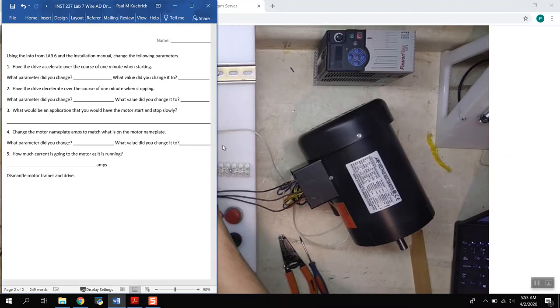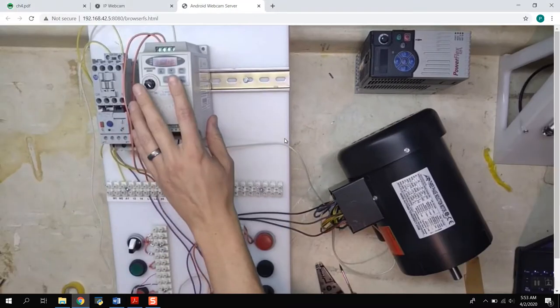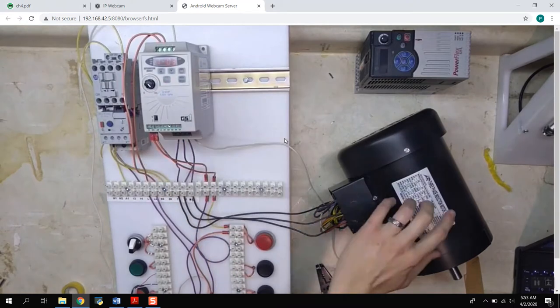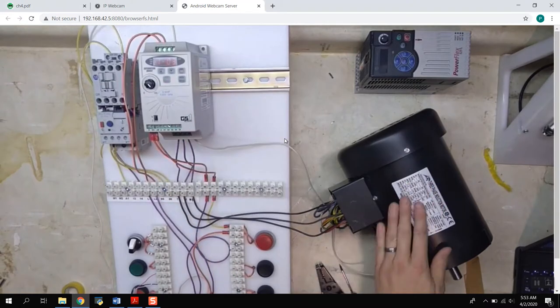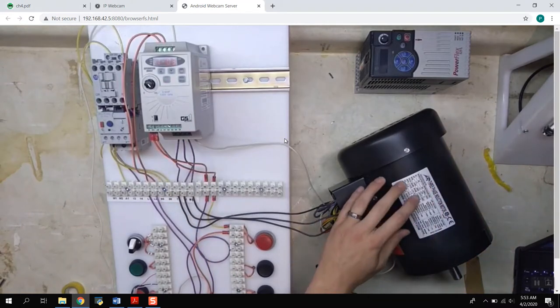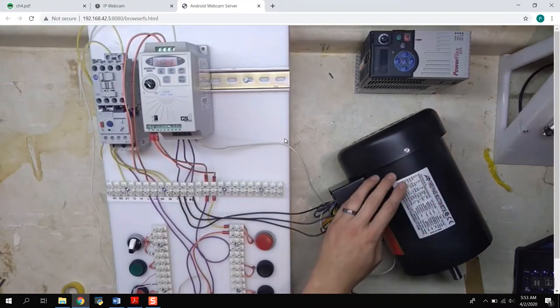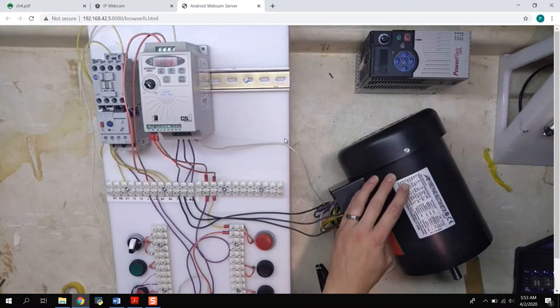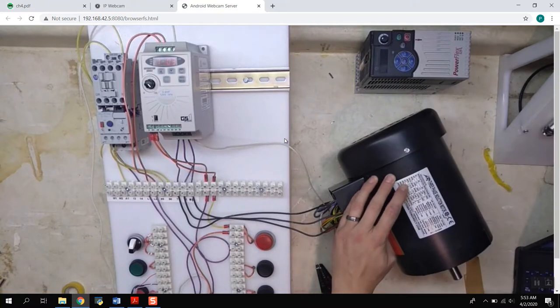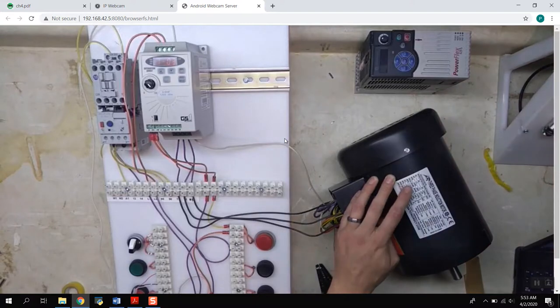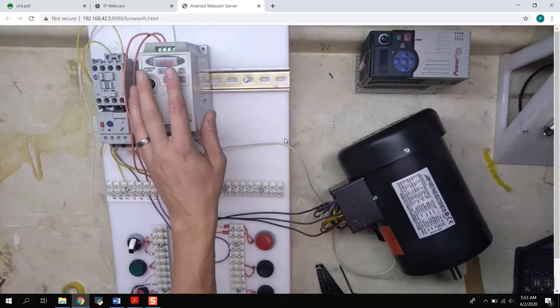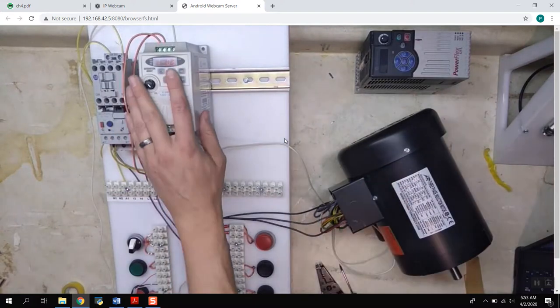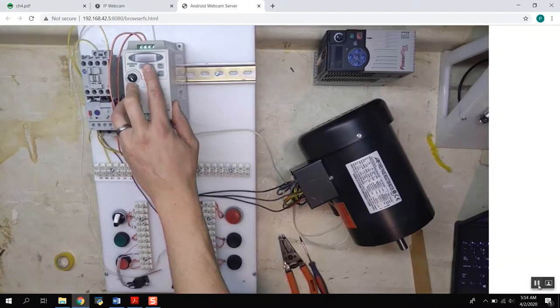So we want to change the settings of the drive to match this. This has a nameplate for current on the low voltage side is 1.7, 1.7 amps. Otherwise that's too much current going to go into the motor and the motor could do damage to the motor. And so we want to make this parameter the parameter on this drive.